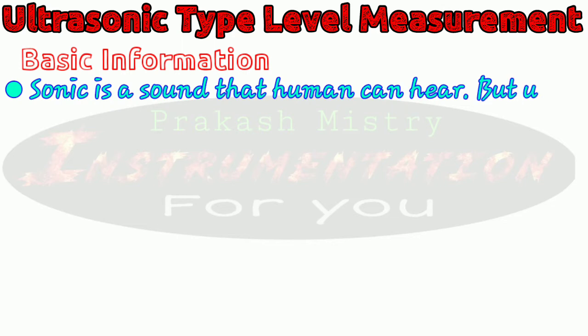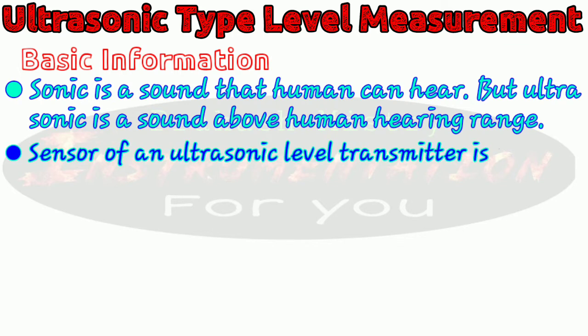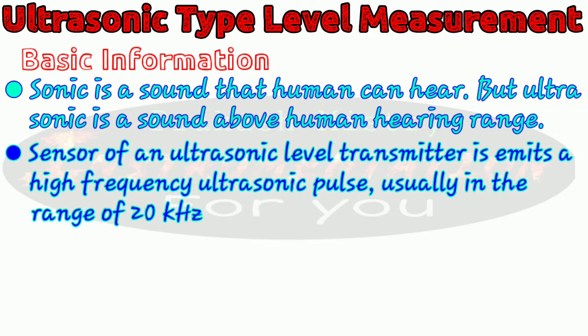Sonic is the sound that we can hear, but ultrasonic is the sound above our hearing range. We can listen up to a maximum frequency of 20 kHz, and ultrasonic frequency is above 20 kHz. The sensor of the ultrasonic level transmitter emits high frequency ultrasonic pulses, usually in the range of 20 kHz to 200 kHz. Lower frequency instruments with higher amplitudes are used for more difficult level measuring applications such as long distance or solid level measurement, while higher frequency instruments are used for shorter liquid level measurement.